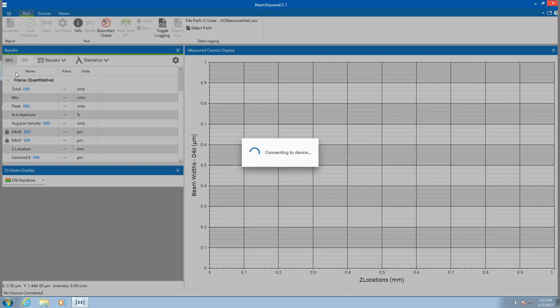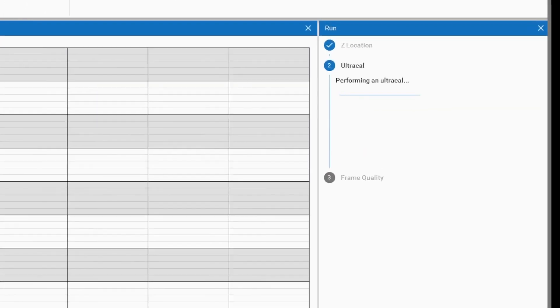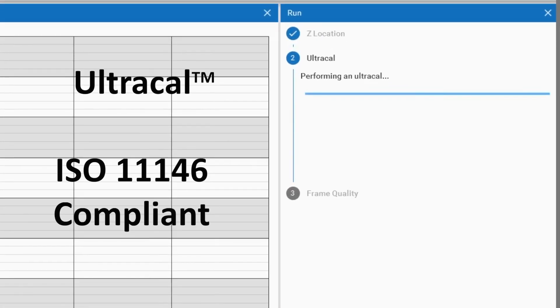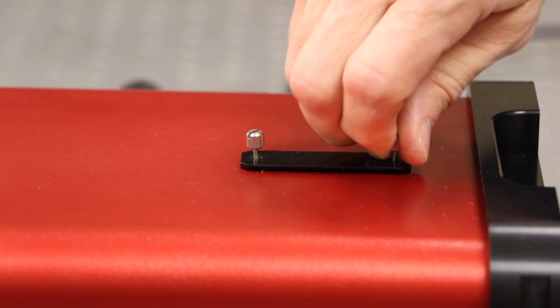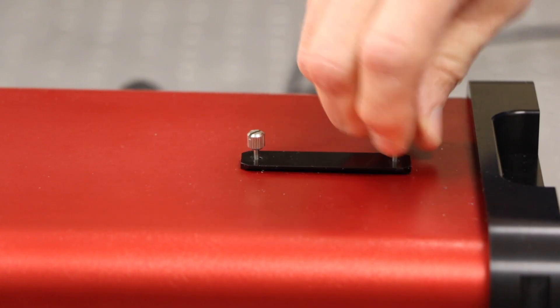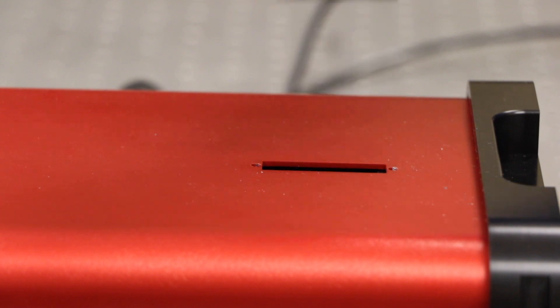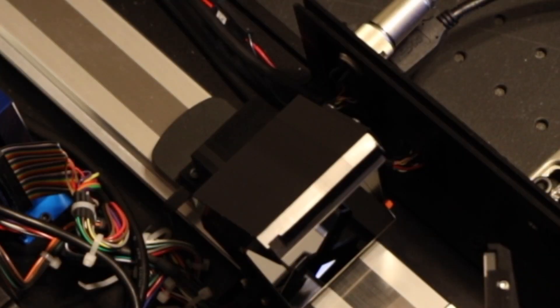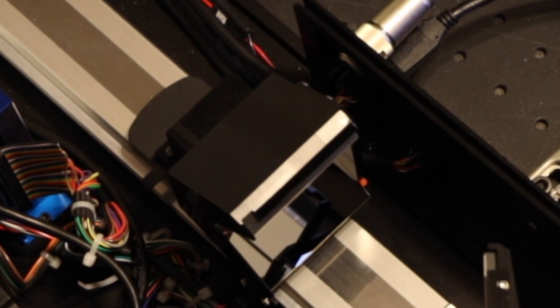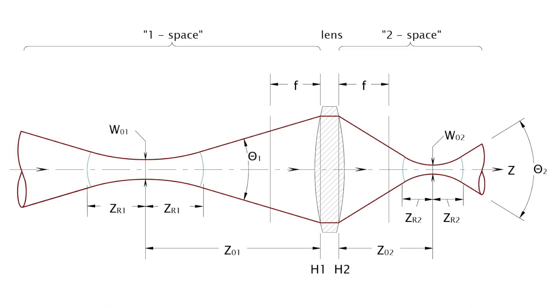Beam Squared is more accurate than competing products because of our patented Ultracal calibration technique and longer optical train. The Beam Squared optical train uses a fixed focal length positioning lens and camera. The mirrors that direct the focused beam into the camera are moved to precise locations, translating the beam through the near field, the waist, and the far field regions.